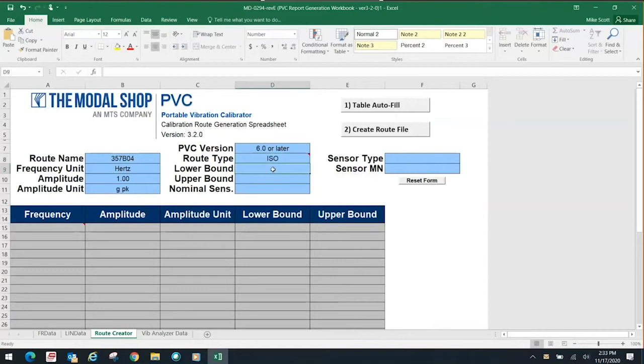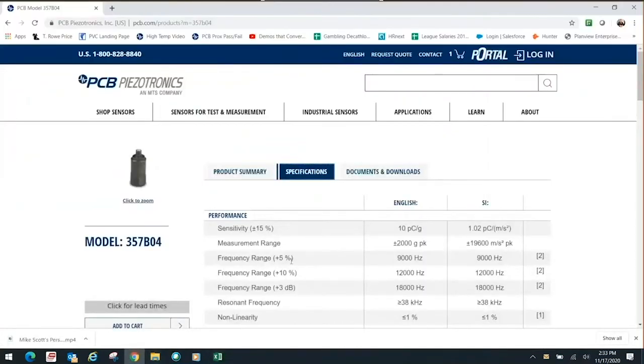All right. And then here is where we enter the upper and lower bound for most of our test points. Now we need to go to the accelerometer specification sheet to look at that. So this is the 357B04 made by PCB Piezotronics, and the output is 10 picocoulombs per G with a 15% tolerance at 100 hertz, which is the reference frequency. Then this sensor needs to stay within plus or minus 5% of whatever you measure at reference frequency. It could be 9.9, could be 10.1.